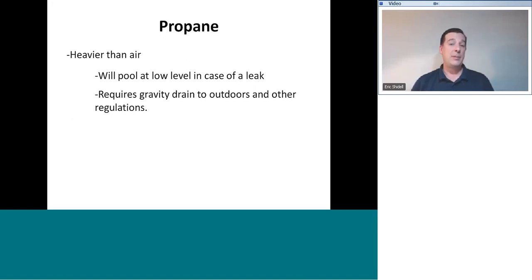In those types of applications, there needs to be a gas sensing device, essentially a stationary gas sniffer that's connected to a safety switch. The safety switch is connected to a solenoid valve that's on the main gas line, and that solenoid is powered open at all times. Unless the gas sniffing device senses the presence of flammable gas, then it will de-energize that solenoid valve on the main gas line, stopping the flow of gas into the structure.